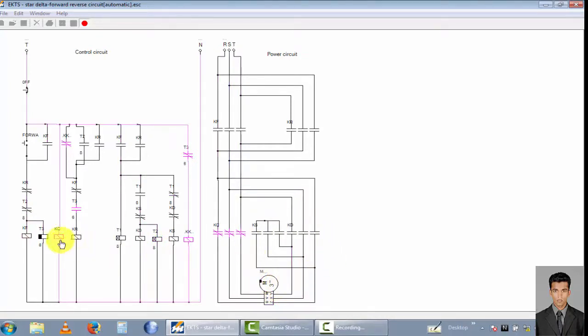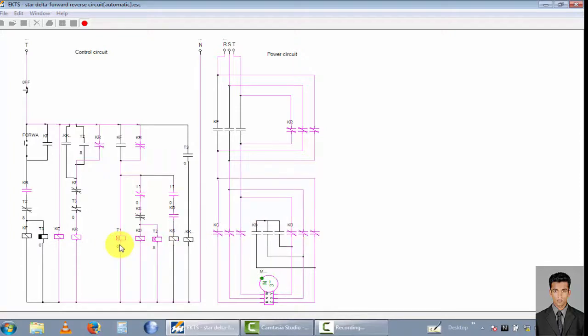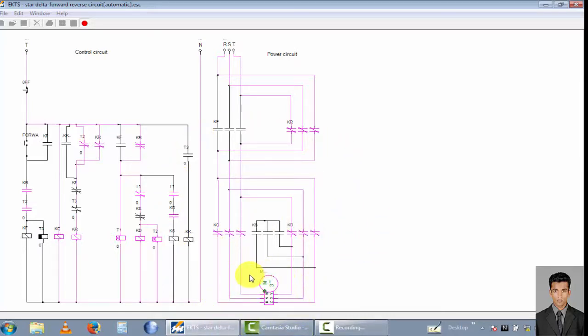Now the motor is stopped. This is the off-time delay timer — it calculates 8 seconds. After 8 seconds, the motor starts in the reverse direction in star connection, and then after another 8 seconds it changes to the delta connection. You can see the motor is rotating in the reverse direction.